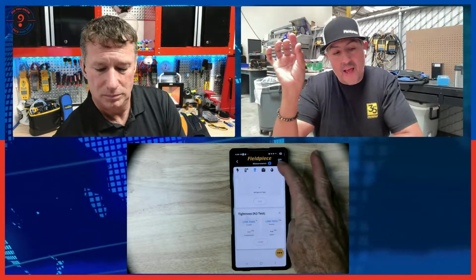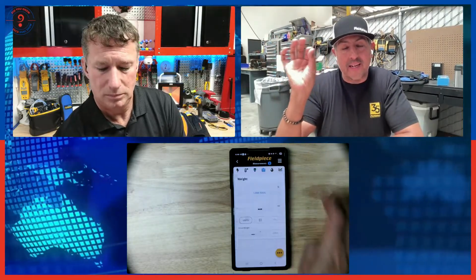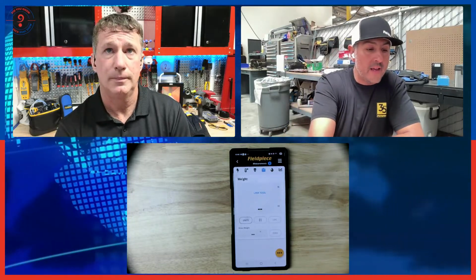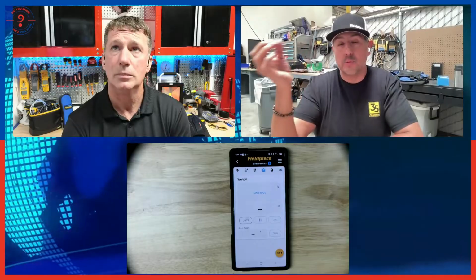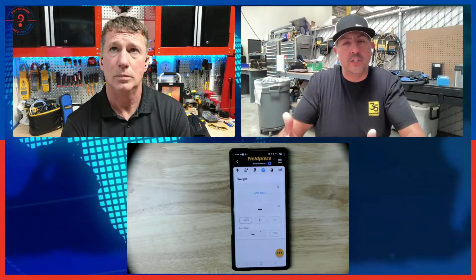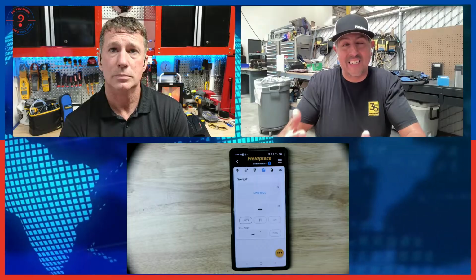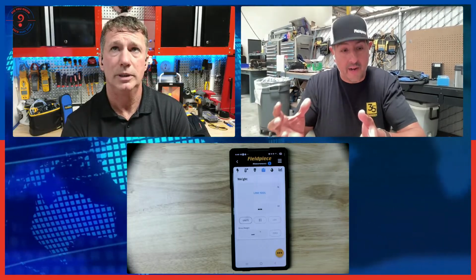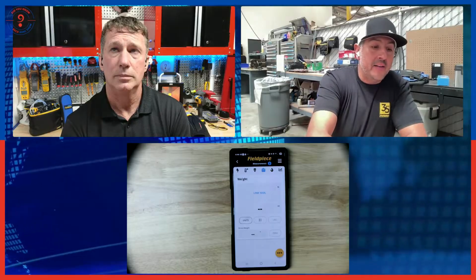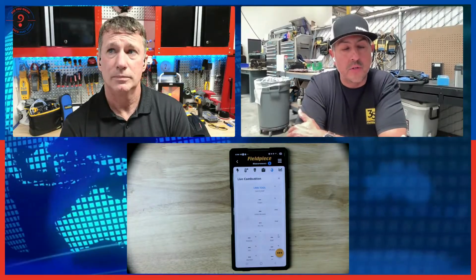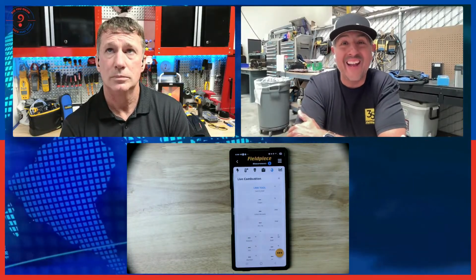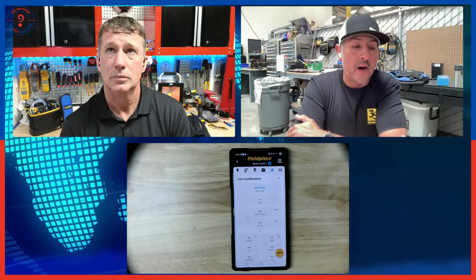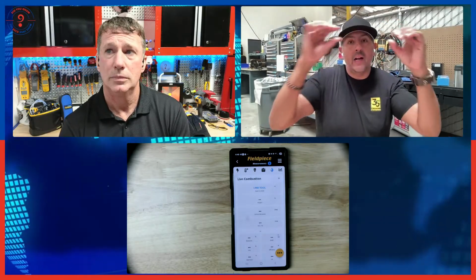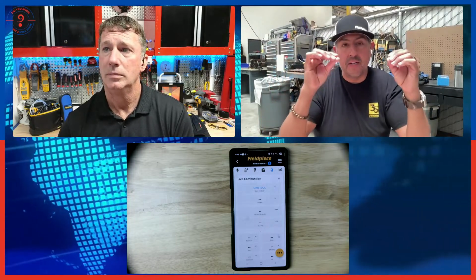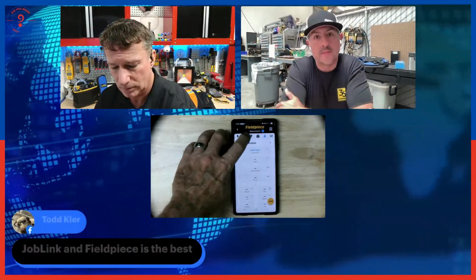And then to finally wrap that up, the next icon looks like a scale. So obviously that's for your refrigerant scale. That's where you can document how much additional refrigerant you needed to charge into the system, because that's a very important thing to document and to keep track of, right? And then towards the end, you see a flame. That's where the combustion analyzer will connect, so you can view the measurements coming from your combustion analyzer and even create a combustion report through the JobLink app as well. So it's categorized by those tabs, and we're just going to jump into that thermometer tab to start connecting some of these tools. Okay. Yeah.